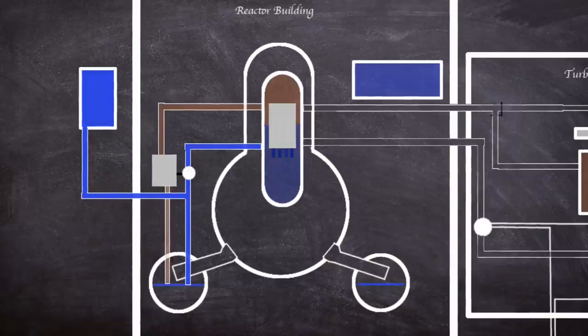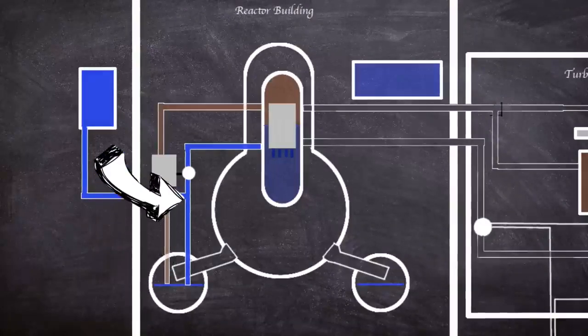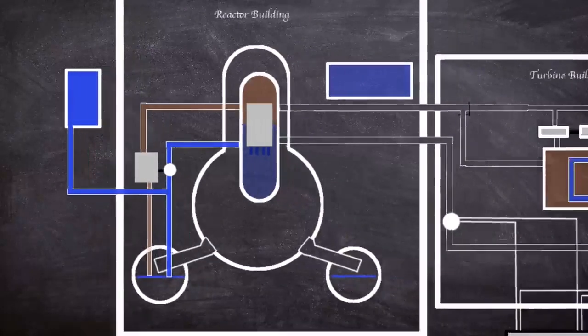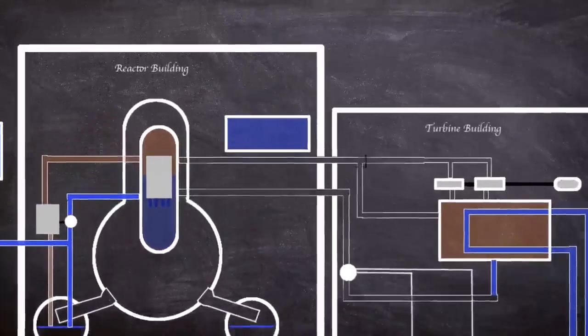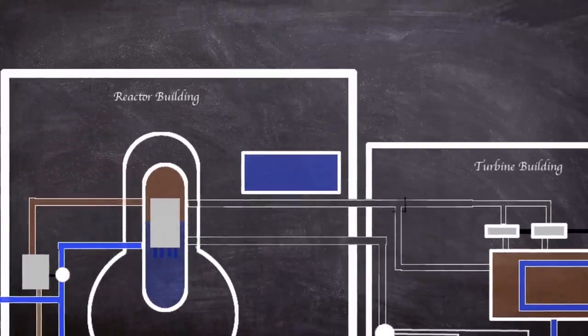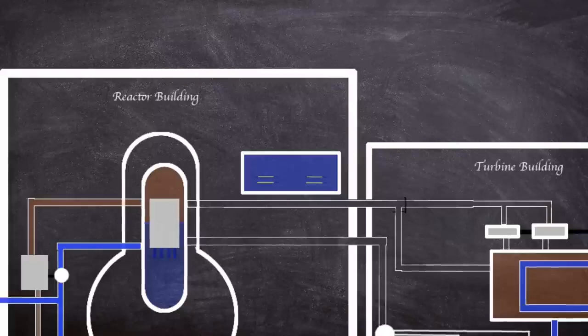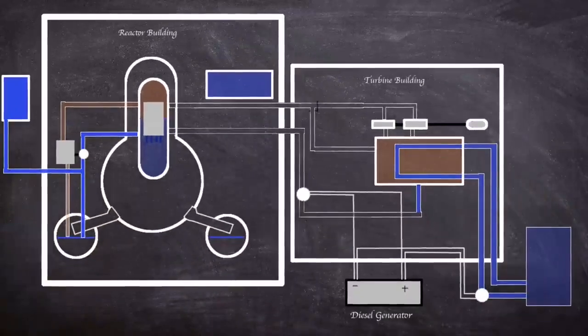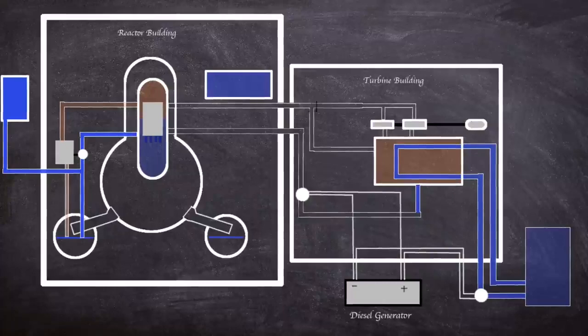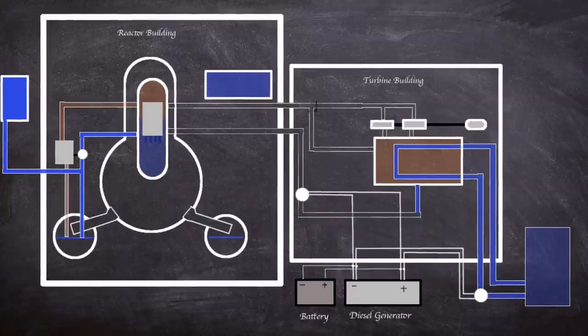The water needed to continue cooling the reactor was supplied from a condensate tank. Once the tank was empty or the suppression pool was full, water was then supplied from the pool for cooling. However, not only the operating reactors on the 11th of March had decay heat. During refuelling, the spent fuel rods are placed in pools near each reactor. These are also still hot so effective cooling is normally provided by electrical power.